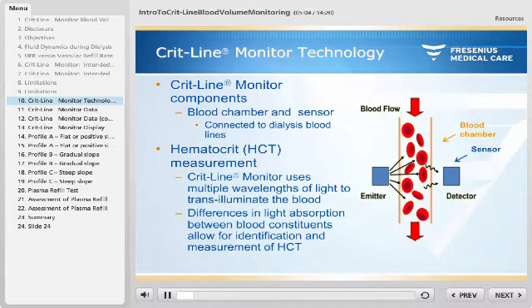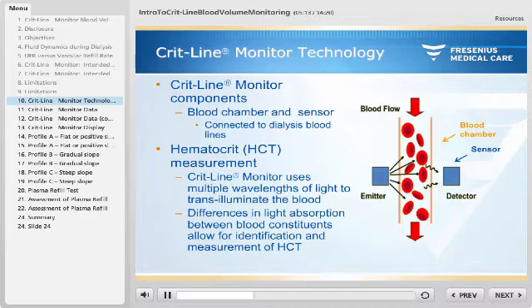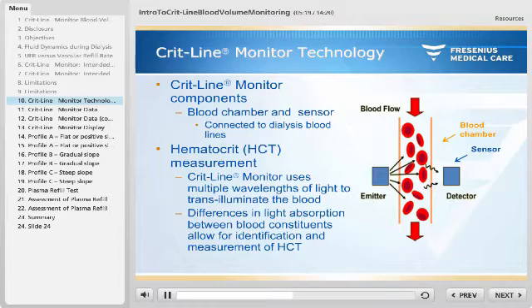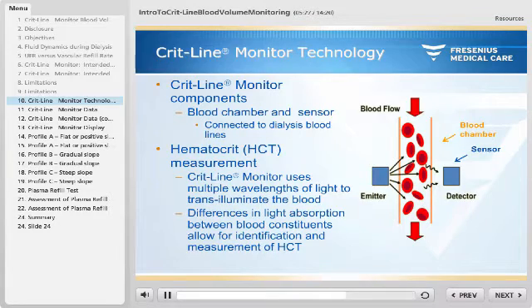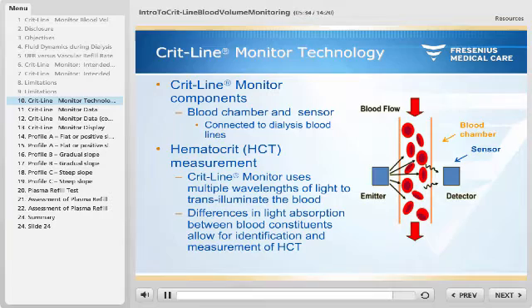The CRITLINE monitor has two components for performing its measurements: a blood chamber connected to the dialysis bloodlines, and a sensor that emits and detects light. To obtain the hematocrit measurement, the CRITLINE monitor uses multiple wavelengths of light to transilluminate the blood. The differences in light absorption between blood constituents allow for identification and measurement of the hematocrit.